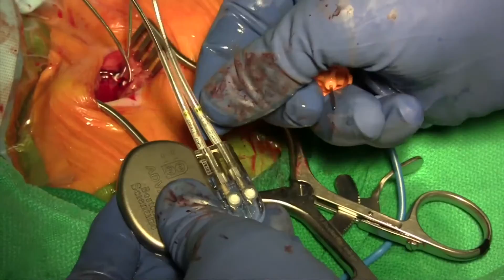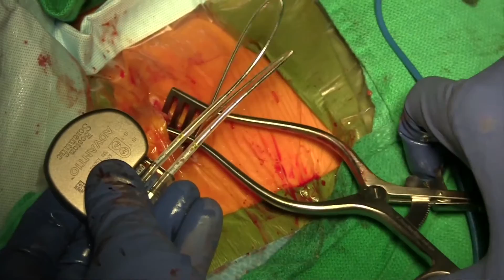That's to make sure that the upper chamber and the lower chamber, the dual device, are operating in synchrony with each other. So what the lower chamber does follows what the upper chamber does. So you have the proper sequence of activation that sort of replicates what happens under the normal circumstance. And again, the pacemaker is really not any bigger, is it? Not much, no. They just keep getting smaller and smaller, don't they?